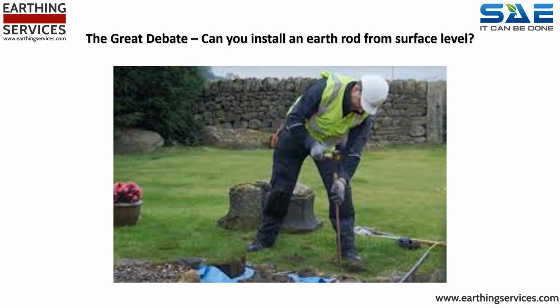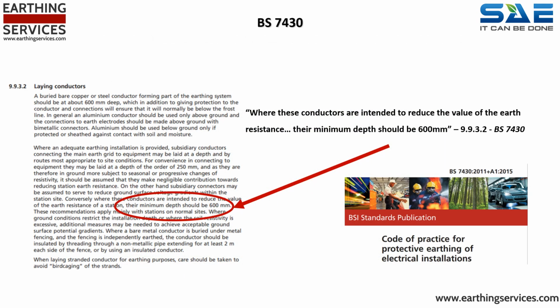The great debate. Can an earth rod be installed from surface level and still be compliant with governing standards? The wiring regulations cite BS 7430 as cross-reference for earthing matters. BS 7430 states, where these conductors are intended to reduce the value of the earth resistance, their minimum depth should be 600 millimeters. As such, any party relying on earth rods must first excavate down to this starting depth before commencing driving earth rods.